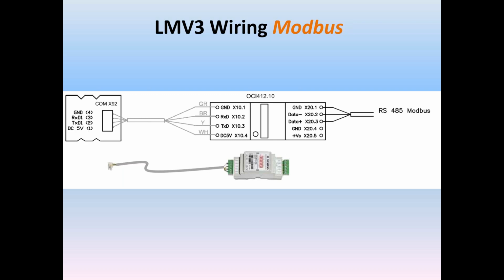Whenever you use a Modbus module, there's optical isolation to prevent damage from the building automation or any other interface device to the LMV3. So that optical isolation takes place in the OCI, and you're going to have to provide a power supply to the Modbus side of the module. This power can either be a typical 24 volt DC power supply, or it can actually be a 24 volt AC transformer. Either one will do. The OCI module will then sift off about 5 volts DC that it takes to drive the module and provide the 485 Modbus and the communication to the LMV3.